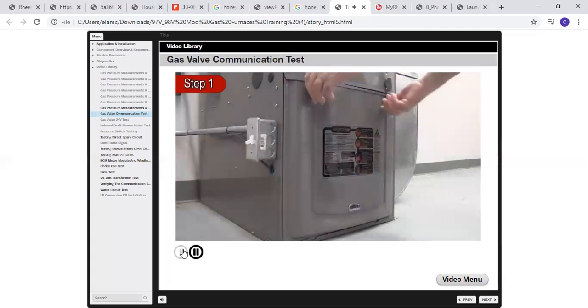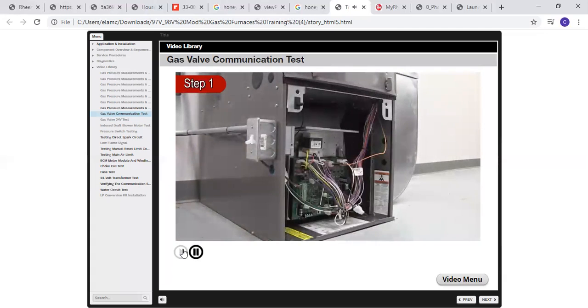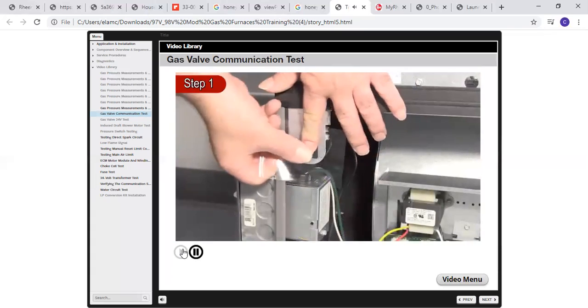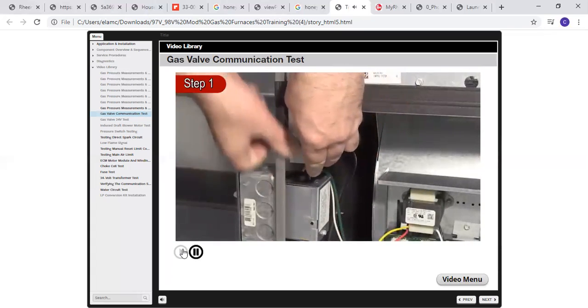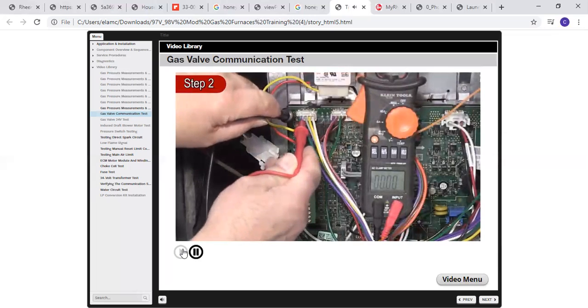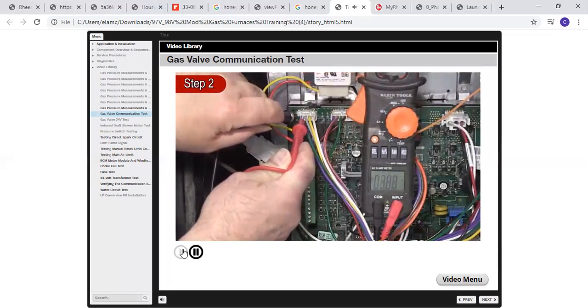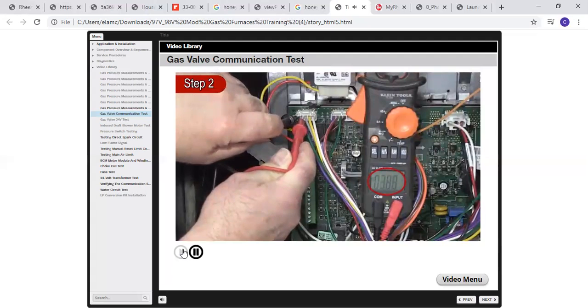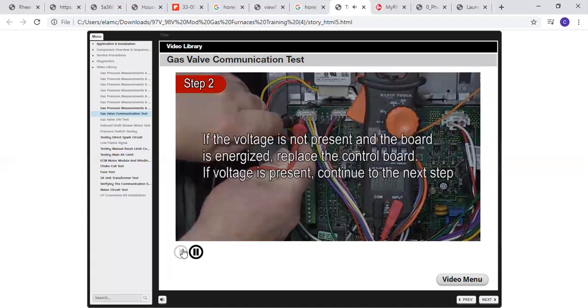Gas valve communication test. Step 1. Access the circuit board by removing the blower door and temporarily depressing the door switch. Power will be restored. Step 2. Check for DC voltage between the transmit and ground pins at the integrated control board, purple and green wires. If 3 to 5.5 volts DC is present, the board is transmitting. If the voltage is not present and the board is energized, replace the control board. If voltage is present, continue to the next step.